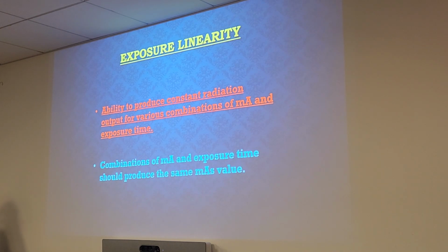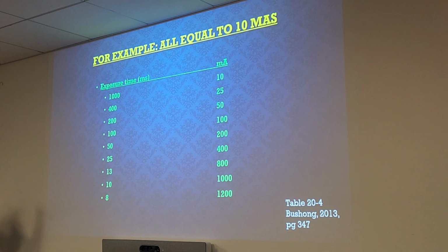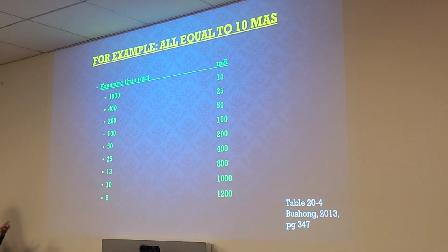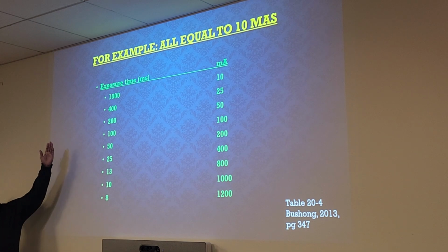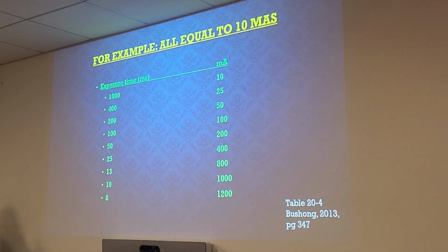So exposure linearity is the ability to produce constant radiation at various mA and exposure times. Meaning no matter what my mA or exposure time is, I should still be able to produce constant radiation output. That's the combination of mA and exposure times, and they should produce the same mAs value. So, for instance, you have an exposure time of 1,000 milliseconds, and you have your mA at 10. So 1,000 times 10 gives you 10,000, which is your 10 mAs. So if the medical physicist is doing the test, he uses these different combinations, and it should give you in the ballpark of 10 mAs.